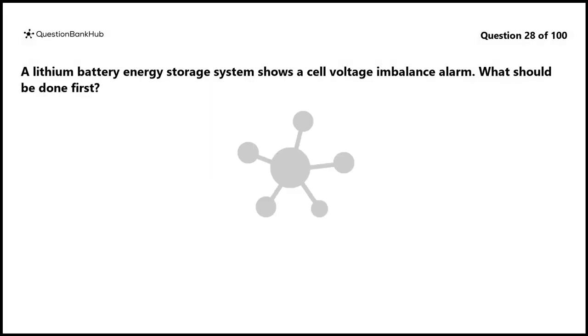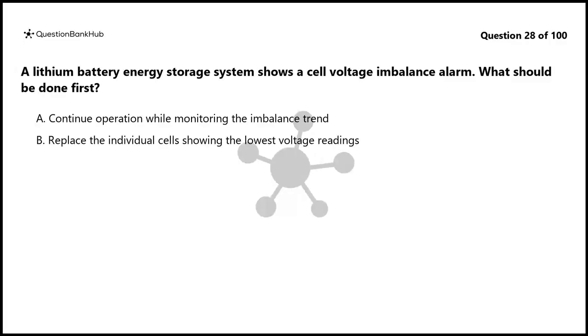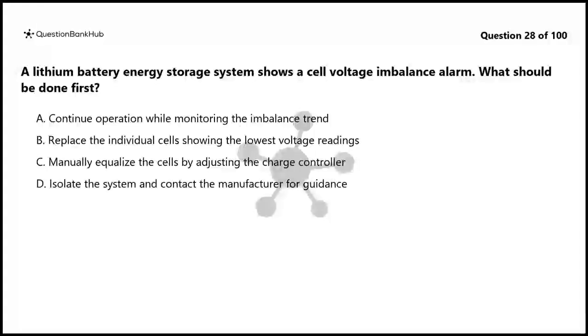Question 28. A lithium battery energy storage system shows a cell voltage imbalance alarm. What should be done first? A. Continue operation while monitoring the imbalance trend. B. Replace the individual cells showing the lowest voltage readings. C. Manually equalize the cells by adjusting the charge controller. D. Isolate the system and contact the manufacturer for guidance.